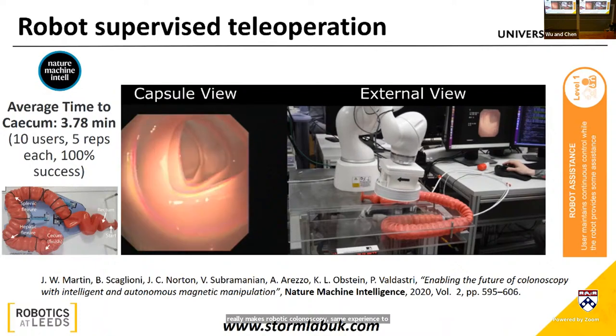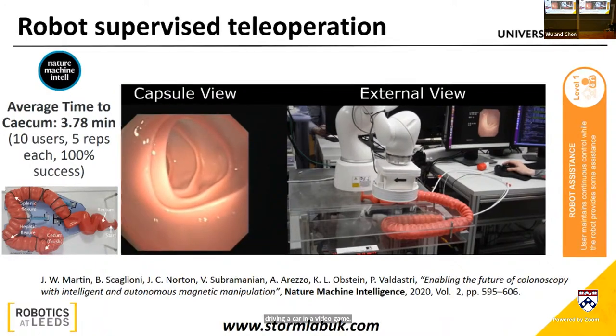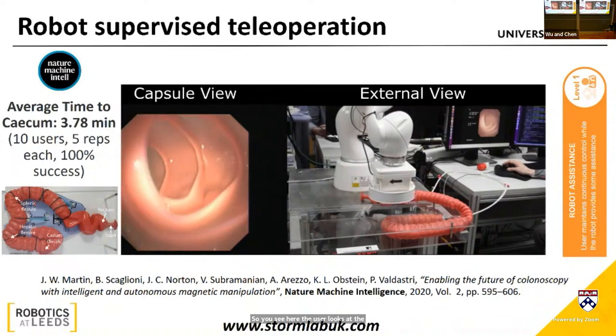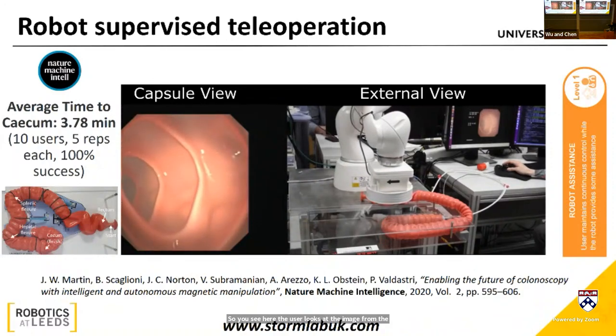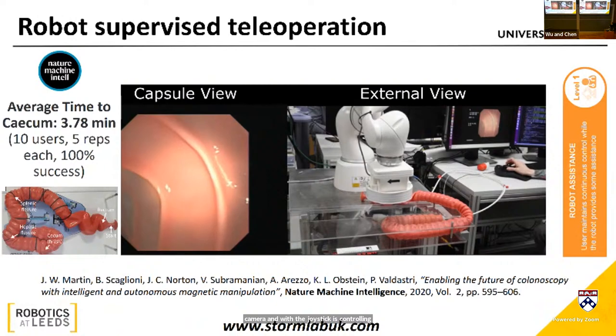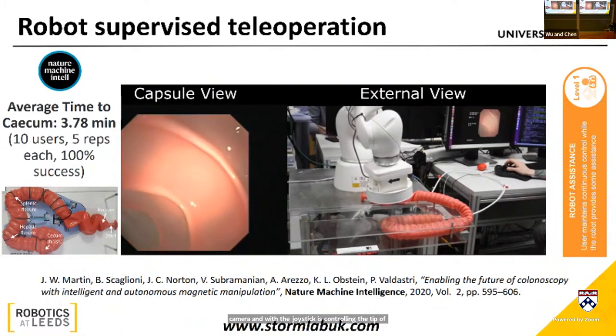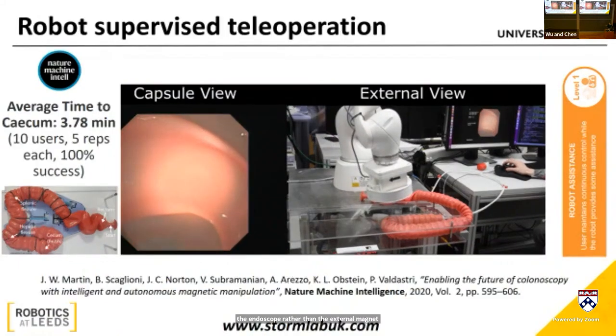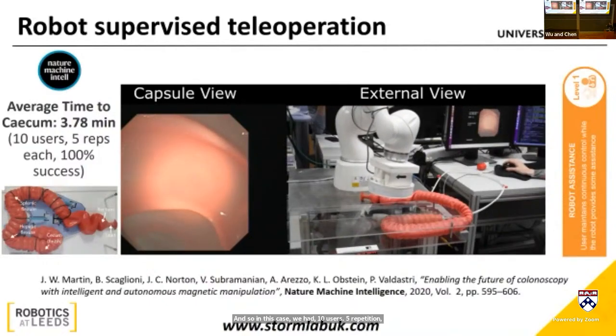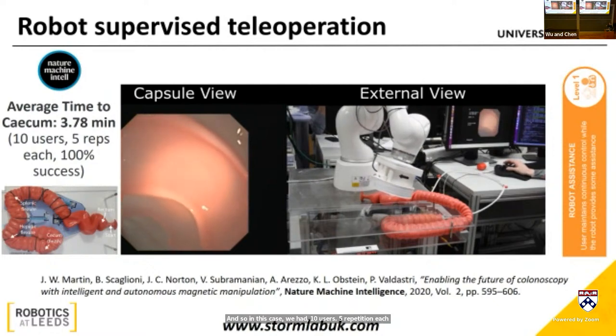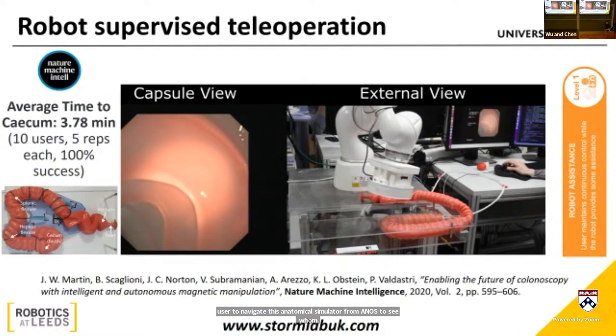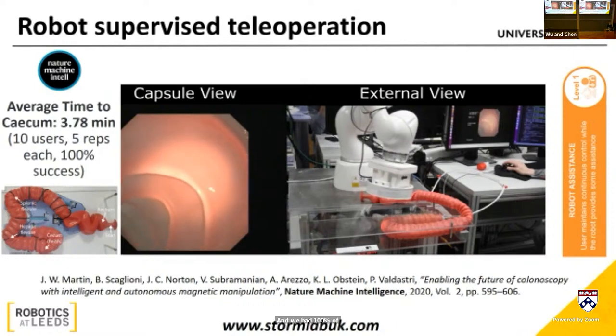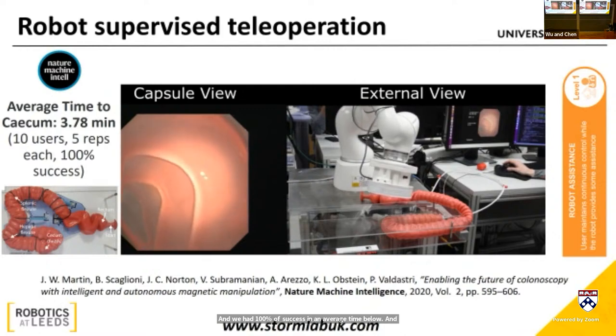So you see here, the user looks at the image from the camera and with the joystick is controlling the tip of the endoscope rather than the external magnet. In this case, we had 10 users, 5 repetitions each, navigating this anatomical simulator from anus to cecum, and we had 100% success in an average time below 4 minutes. This was really encouraging for us.